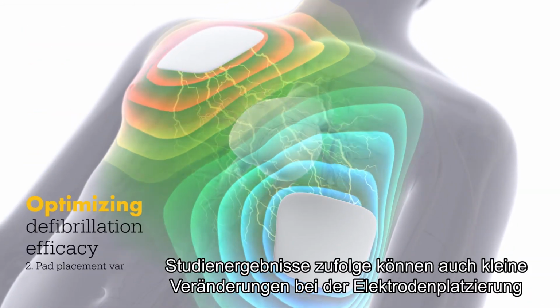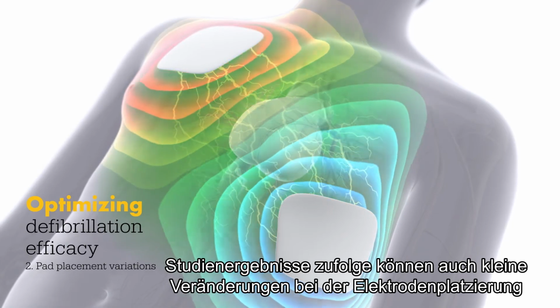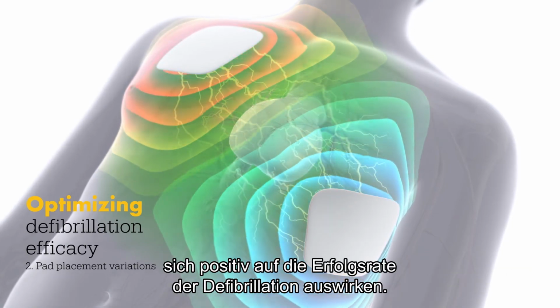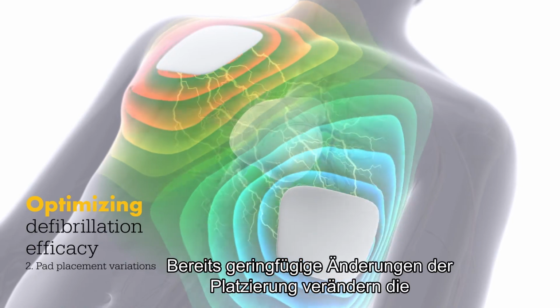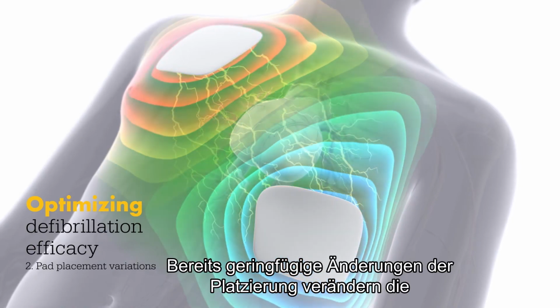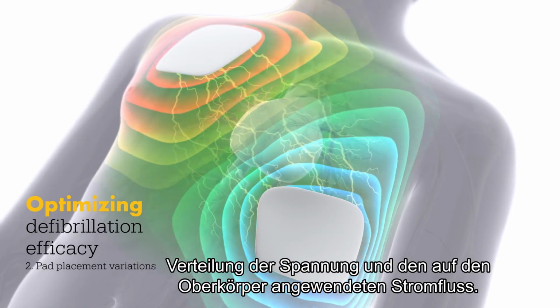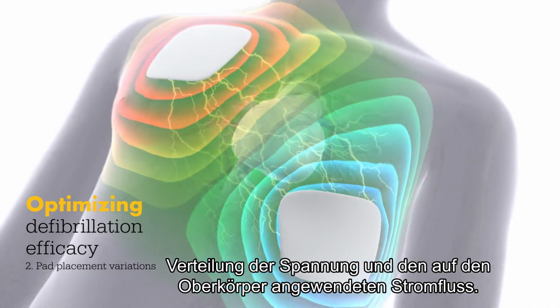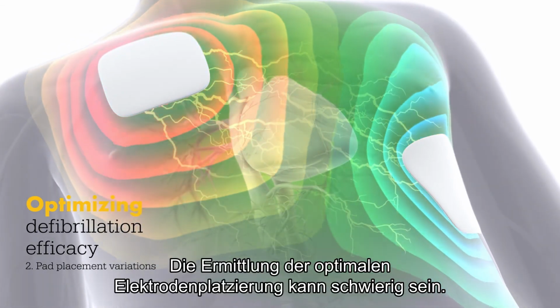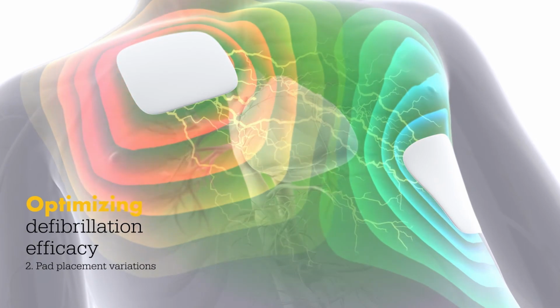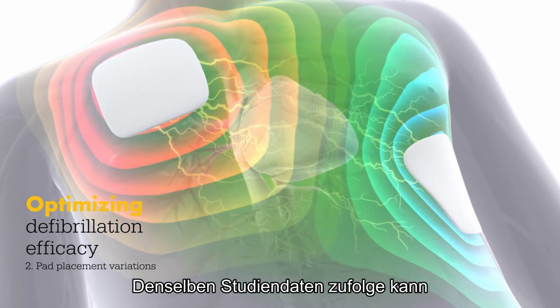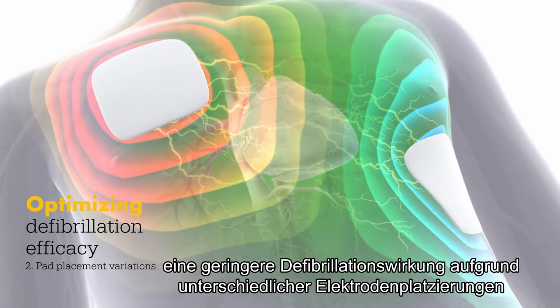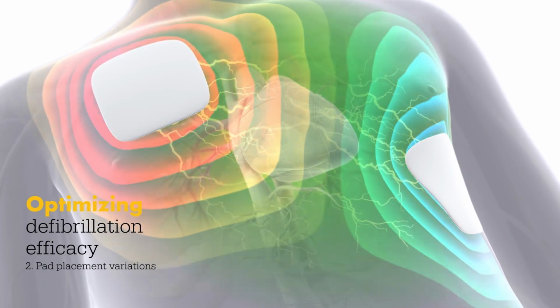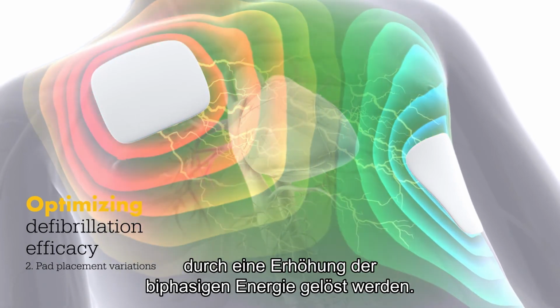Research also reports that small variations in pad placement can impact defibrillation success rate. Varying the pad placement, even by small amounts, changes the distribution of the voltage and current flow applied to the torso. Predicting the optimal pad placement can be difficult. The same data also reports that lower defibrillation efficacy from pad placement variations were overcome with higher biphasic energy.